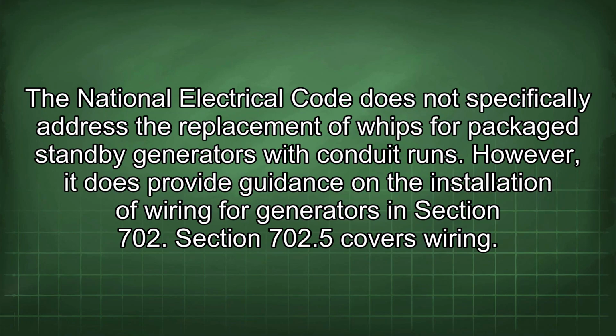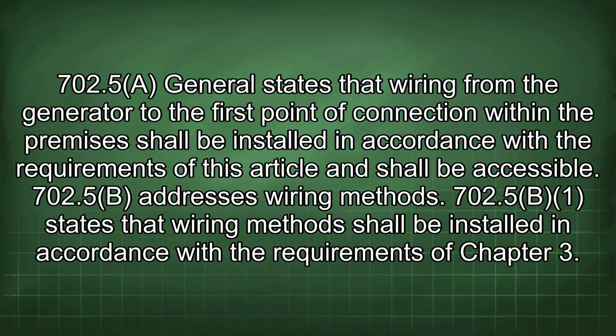The National Electrical Code does not specifically address the replacement of whips for packaged standby generators with conduit runs. However, it does provide guidance on the installation of wiring for generators in Section 702. Section 702.5 covers wiring. 702.5(A) general states that wiring from the generator to the first point of connection within the premises shall be installed in accordance with the requirements of this article and shall be accessible.